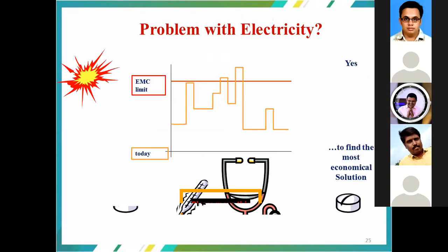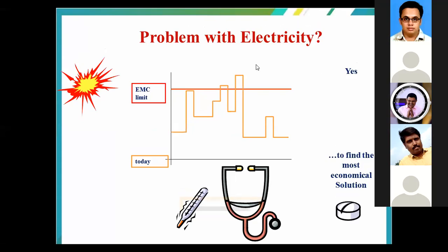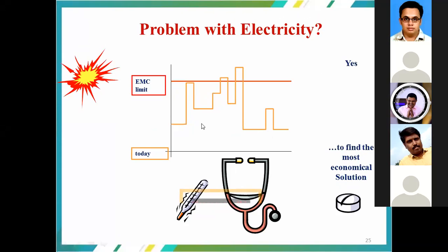And in this case, we have the real-time problem. The EMC limit is already set, whereas the measured values exceed the prescribed EMC limit, and thereby we are supposed to go for a solution. We are supposed to find the remedial measures such that we maintain the distortions within the prescribed limit. If we are not going for remedial actions, it will have a cumulative effect, which is injurious to the electrical network.